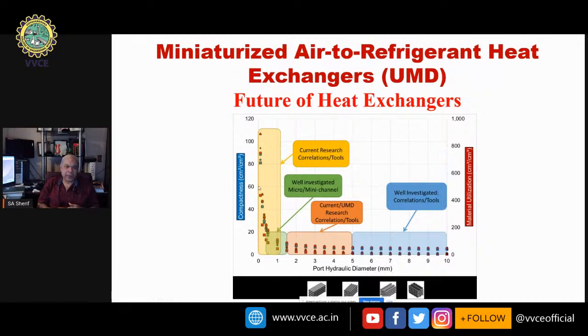Compactness is measured in centimeters squared per centimeter cubed, so the smaller the number, the worse—you want a big surface area for a given volume, so you want to be at the top. You want to be at the very top left corner for high compactness, but if you also want a small hydraulic diameter, you want to be toward the bottom left. Combining both objectives, you want to be at the top left, with a small hydraulic diameter port and high compactness.